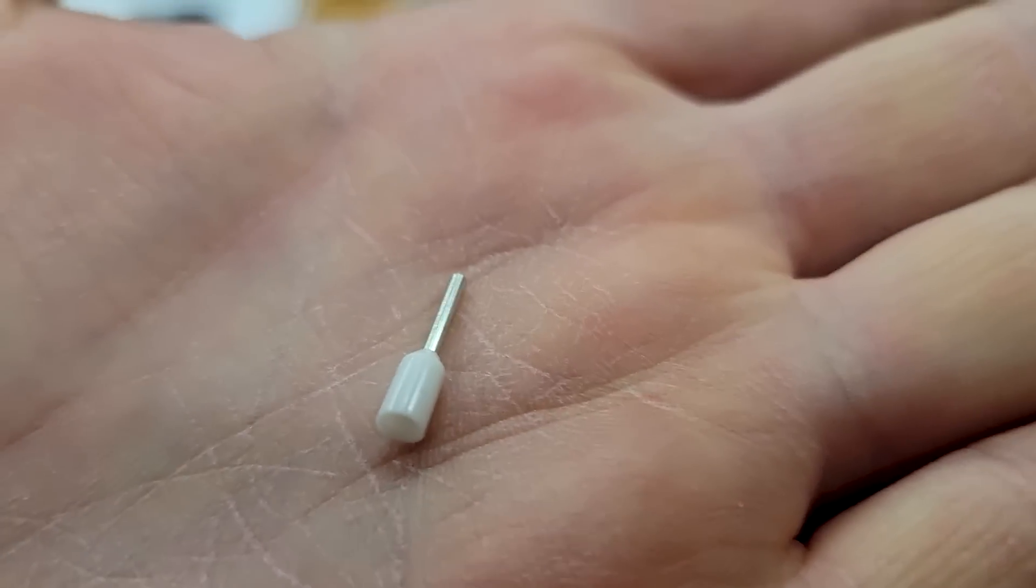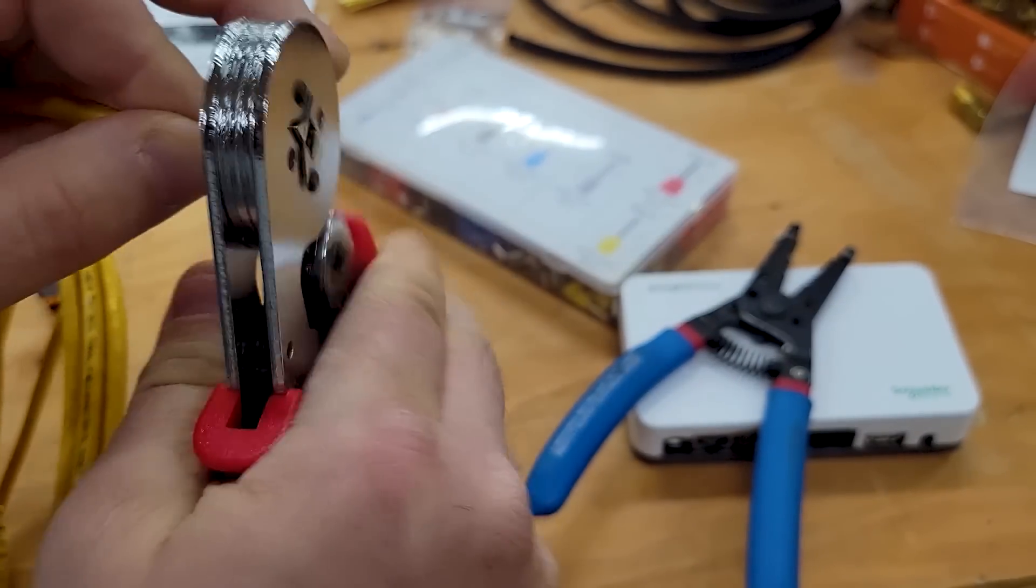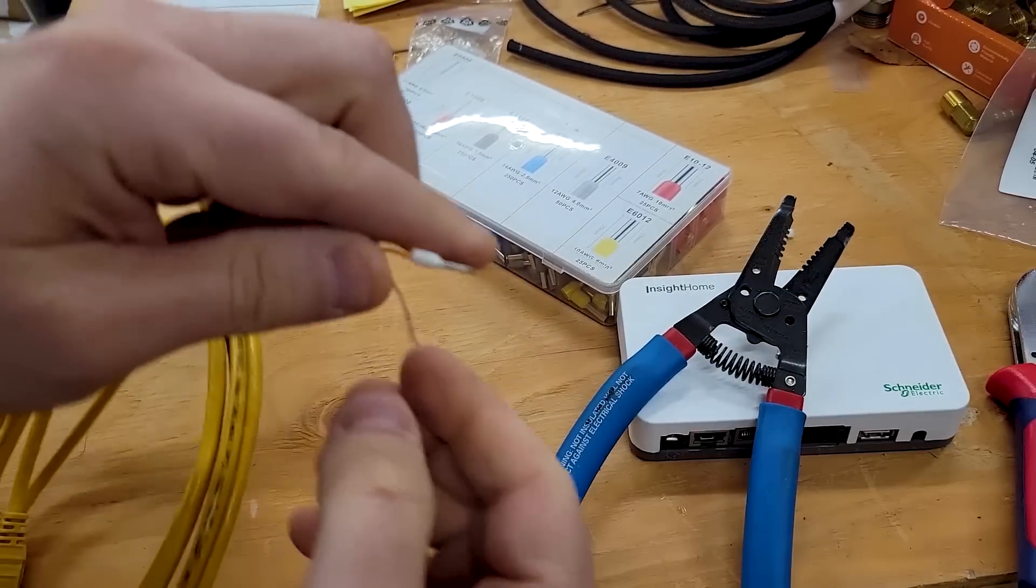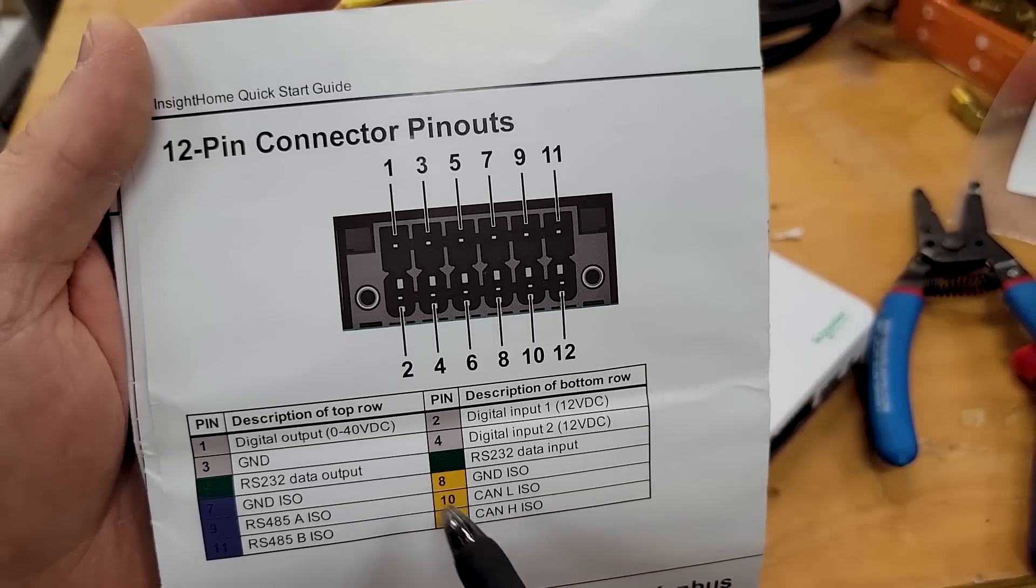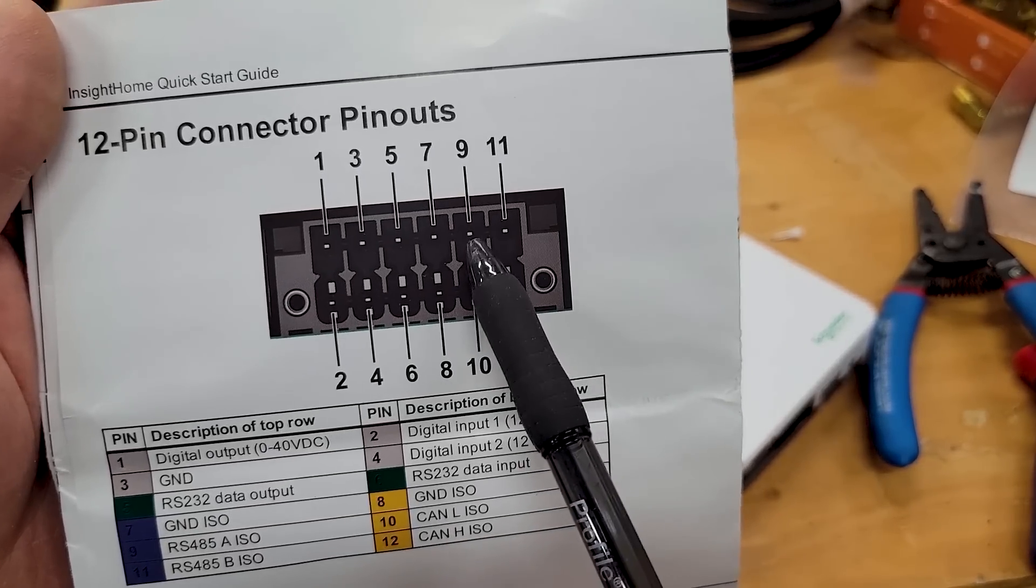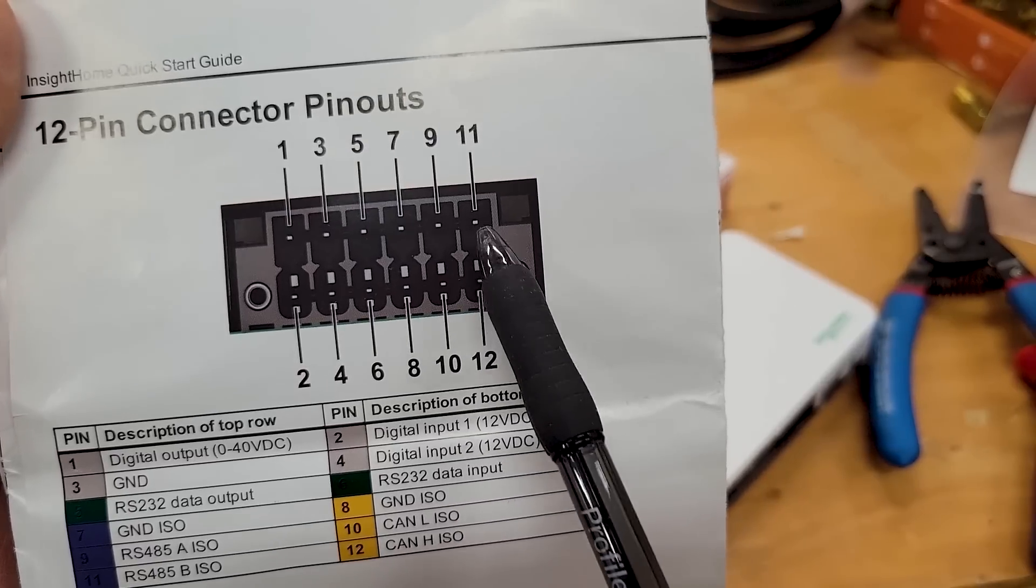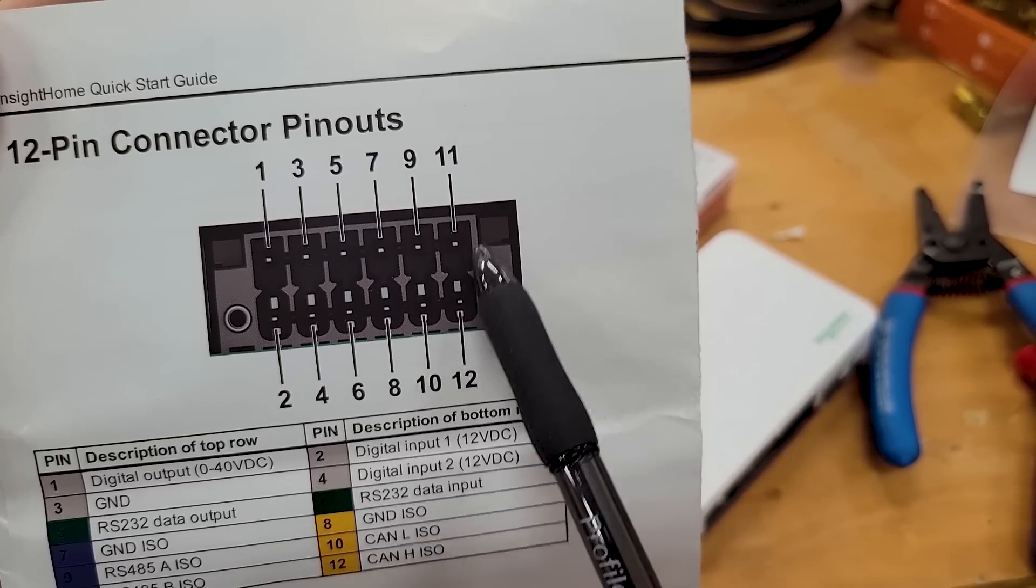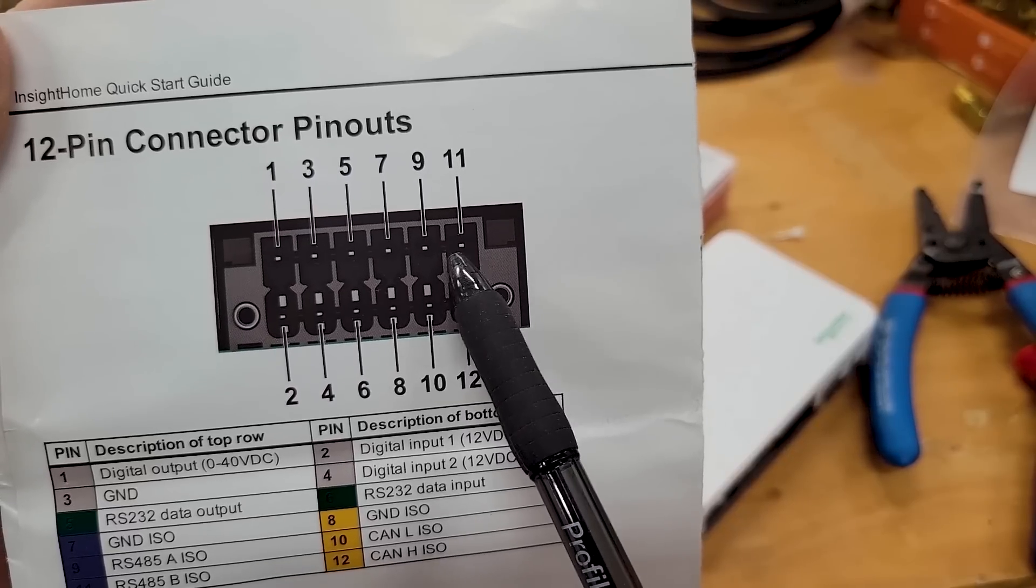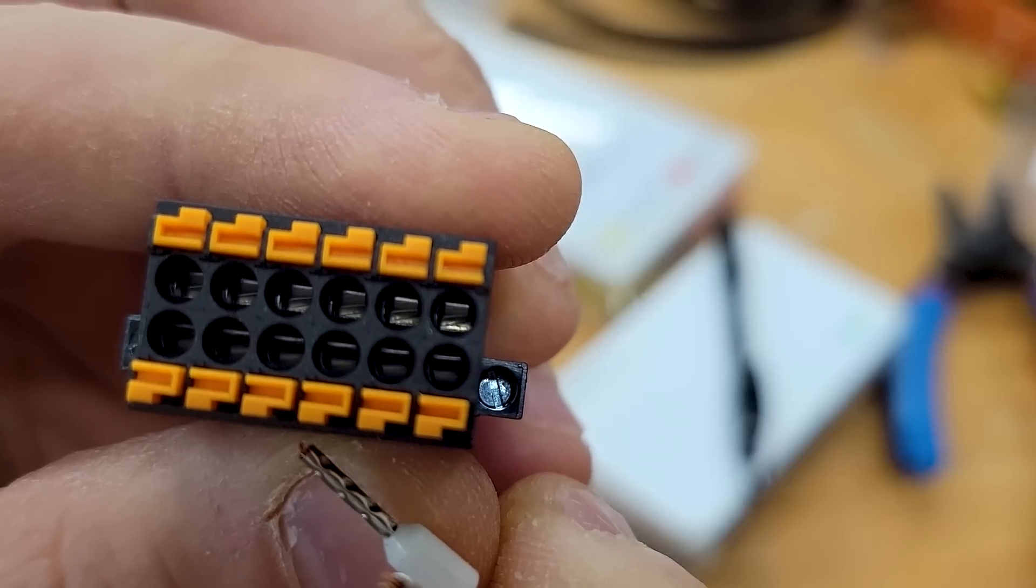This is a little tiny ferrule. This is the quick start guide that came with the Insight Home. Pin number 9 and 11 are the RS485. So those are the two that we want to use. And I think according to the video that I saw from Signature Solar, this one is going to have the white with an orange stripe. And then 9 is going to be the solid orange. So see the metal connector inside there? That's what we're going to push into until it clicks.